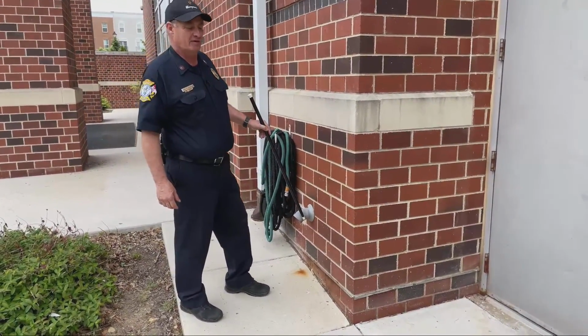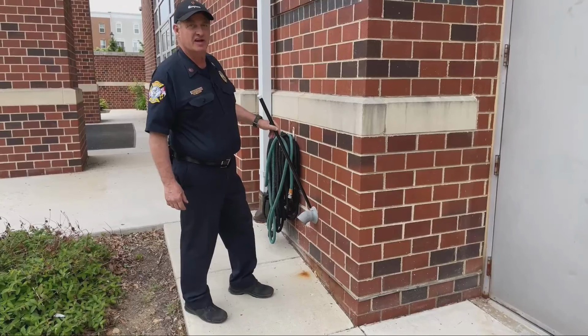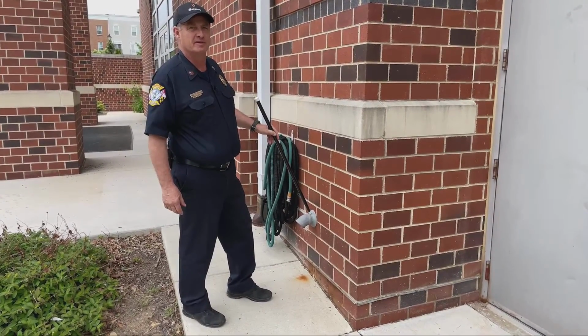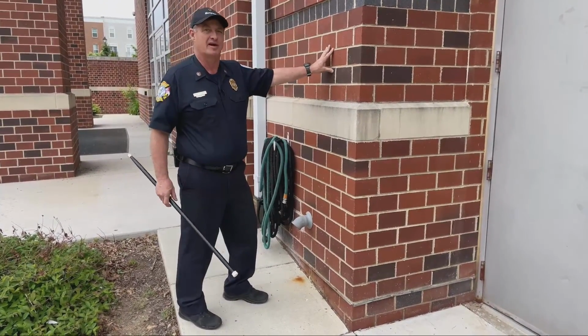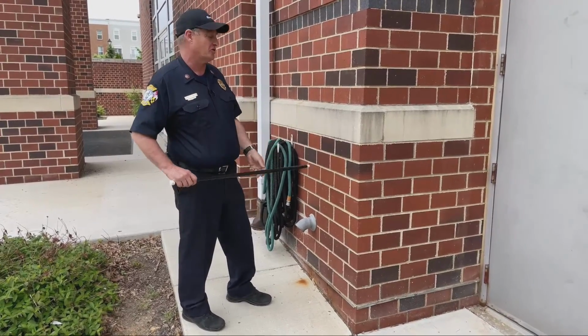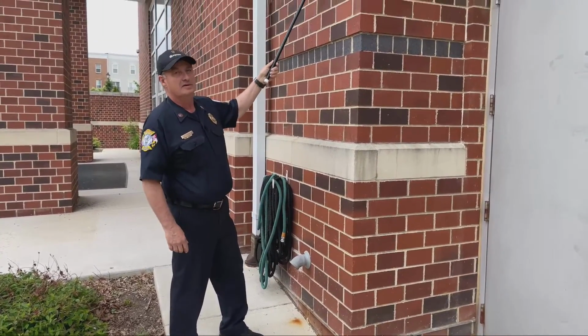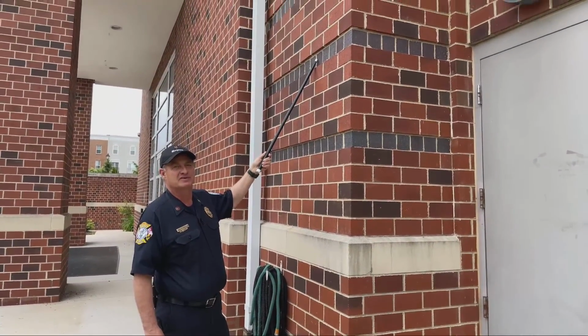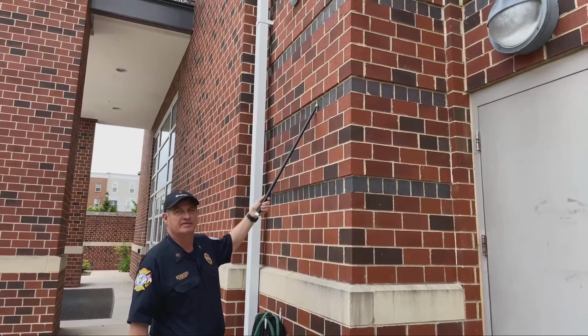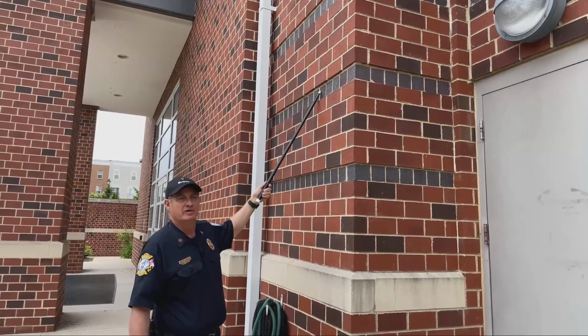The main drain will almost always be on the outside wall just behind the sprinkler room. In this case, the sprinkler room is behind here. Another telltale could be a water motor gong, but in this case, this building does not have one. They've kind of gone out of favor with electric alarms.